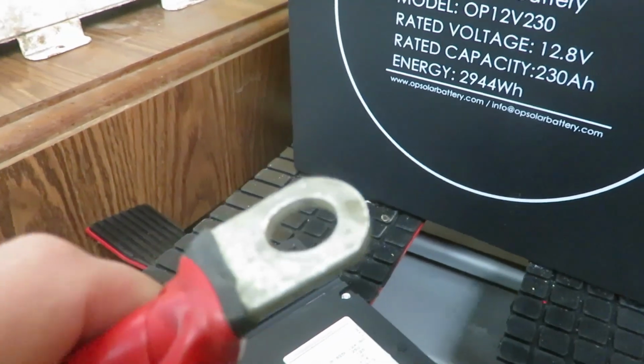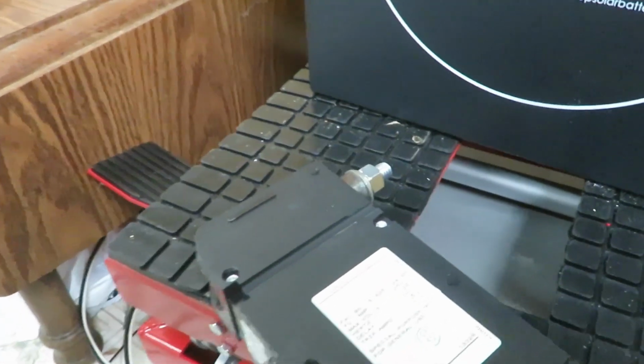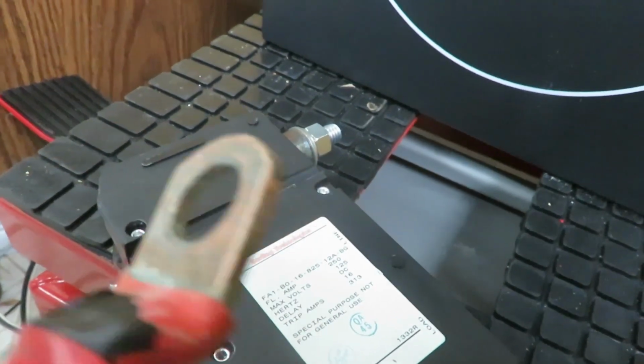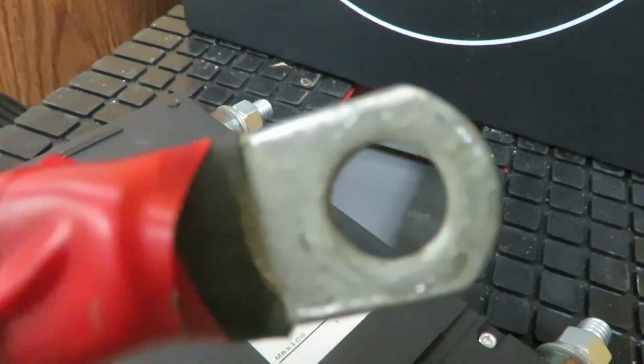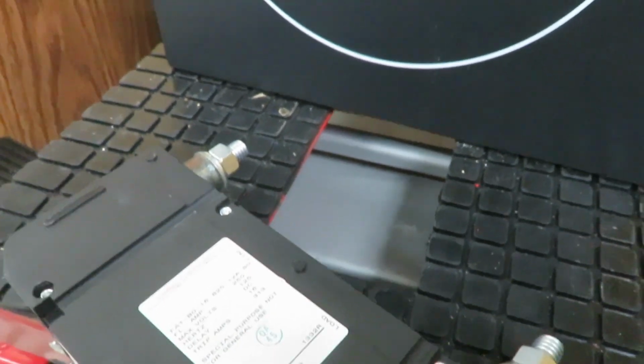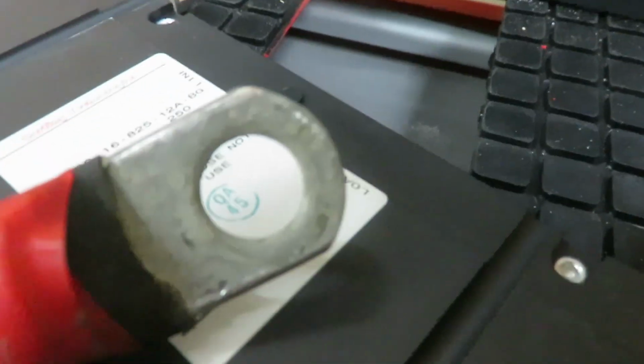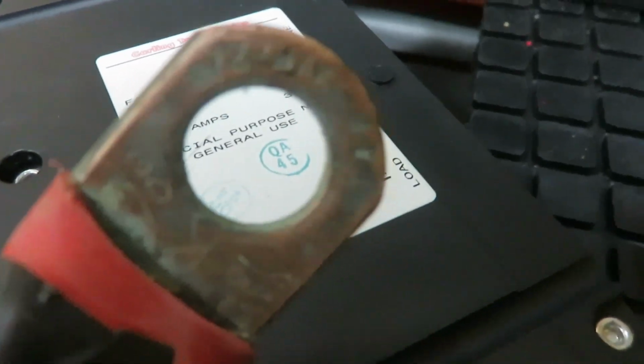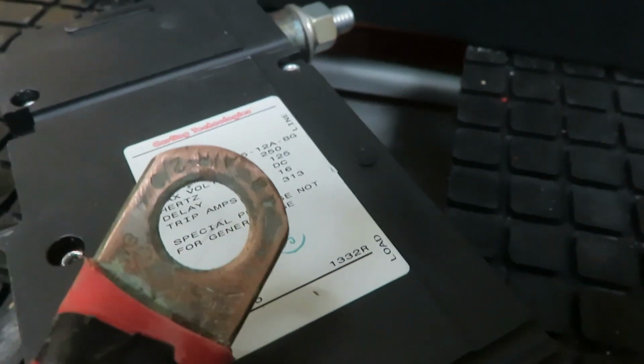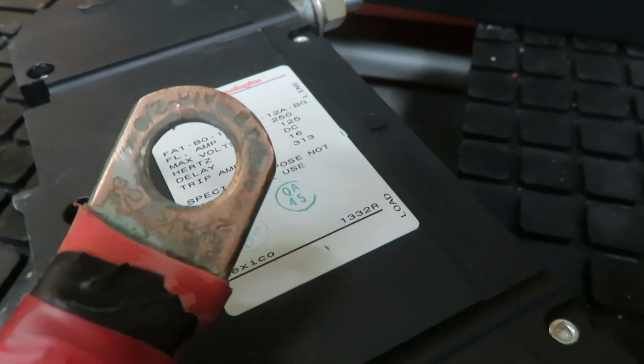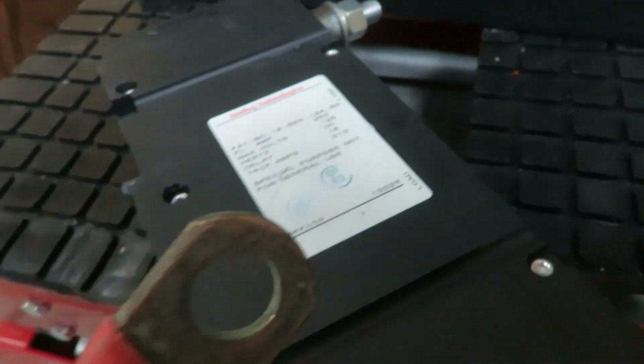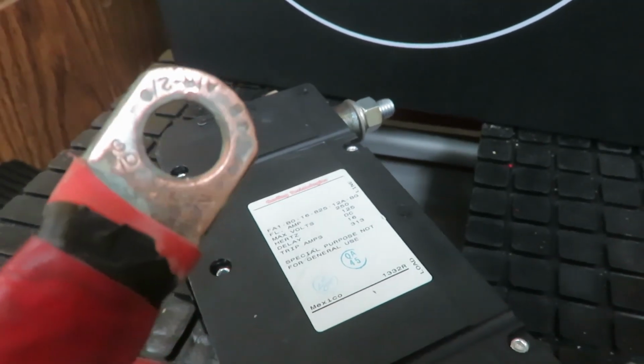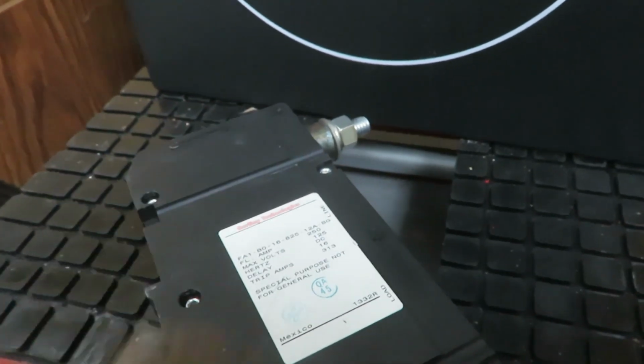The only thing I forgot to mention about these terminals is that some of them you can get are bare copper - it's hard to see in this light, but they're bare copper. You can also get ones that are tinned. The tinned ones aren't going to corrode and oxidize like the bare copper ones will. If they do, it takes just about nothing to clean off. So if you get cables, don't get bare copper ones, or if you do, get them nice and shiny and then put some antioxidant on them, or cover them with something, because you're going to lose some power through a bad connection if it oxidizes at 12 volts.